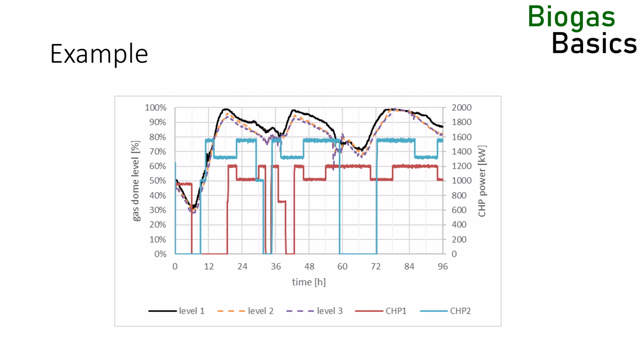We see that the main gas store level fluctuates and the levels of the two ancillary gas storages on the storage tanks follow the main gas storage. The levels in the ancillary gas storages are usually 2 hours behind the main gas storage, but do eventually catch up. The two ancillary gas domes have the same level within 1 or 2%. The plant can make full use of its gas storage.